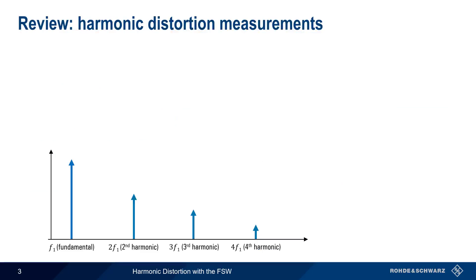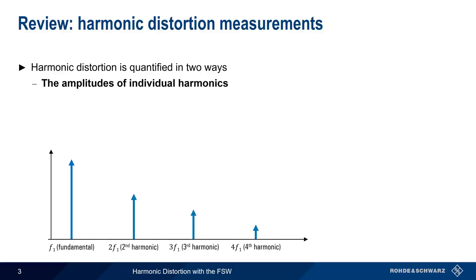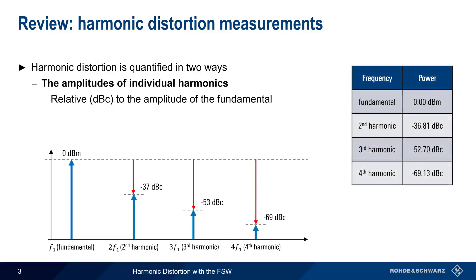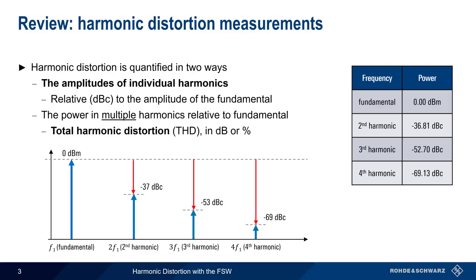Harmonic distortion can be quantified in two ways. The first is the amplitude of the individual harmonics, normally reported as powers relative to the fundamental, so units are typically dBc, or decibels down from the fundamental carrier. In this example, the amplitude of the fundamental is measured as an absolute power in dBm, but the power of each harmonic is reported in dBc relative to this power. The other way is as the combined power in multiple harmonics relative to the fundamental, referred to as total harmonic distortion, reported either as a percentage or in dB.